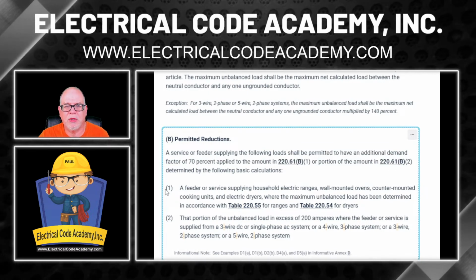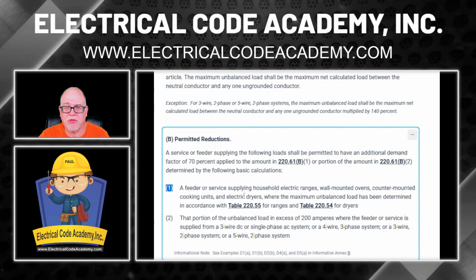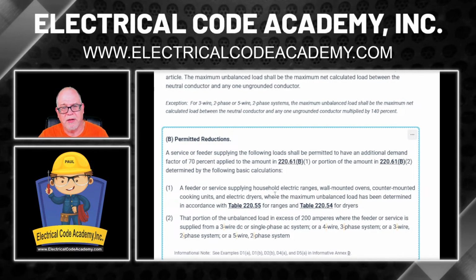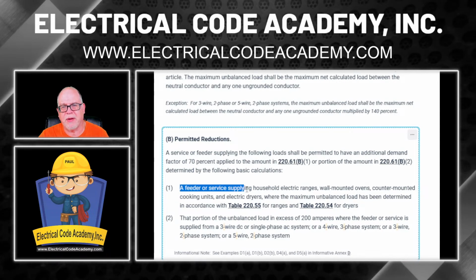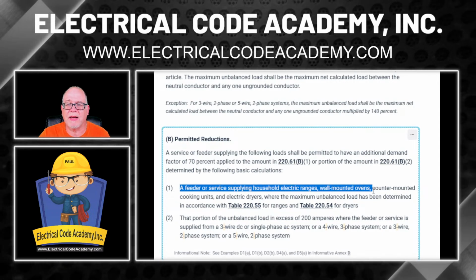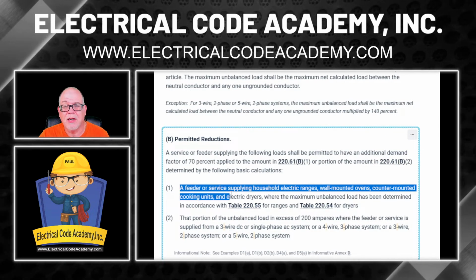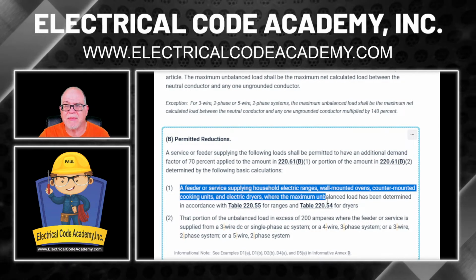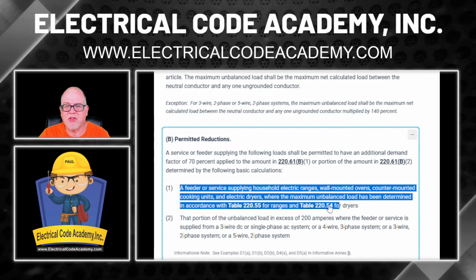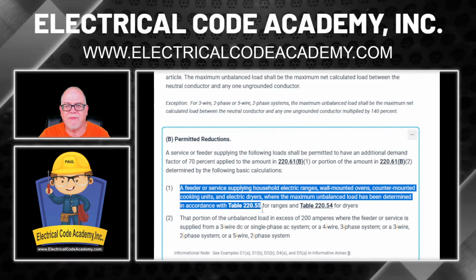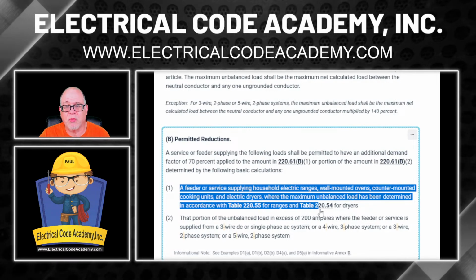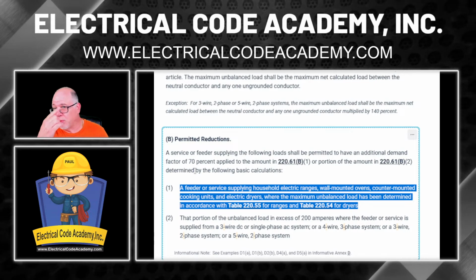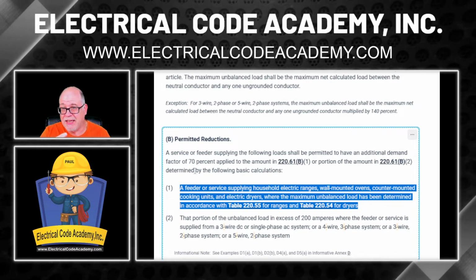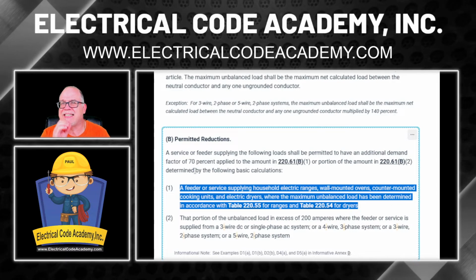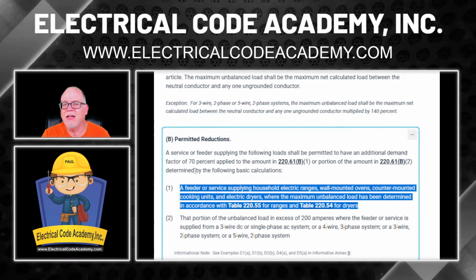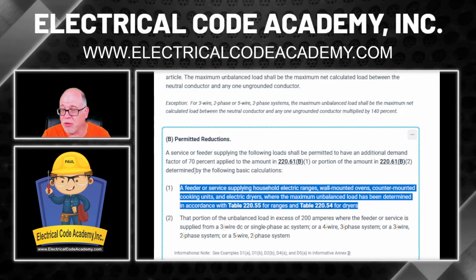All right. Well, we're going to be doing B1 because, as you'll notice right here, electric dryers are in here. So it says a feeder or service supplying household electric ranges, wall-mounted ovens, counter-mounted cooking units, and electric dryers where the maximum unbalanced load has been determined in accordance with Table 220.55 for ranges and Table 220.54 for dryers. Well, we only had one, so that was 5,400. That is our value that we use. So I can take that and I get to apply a 70% additional demand to that.